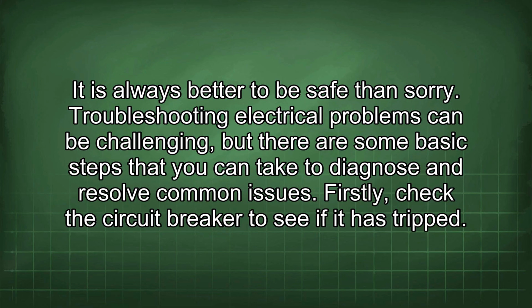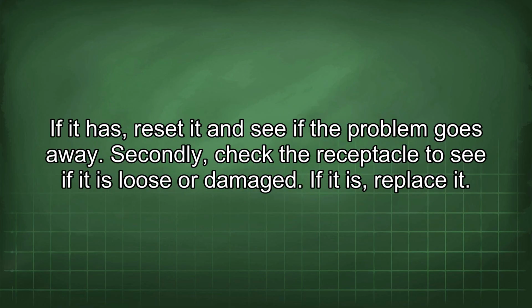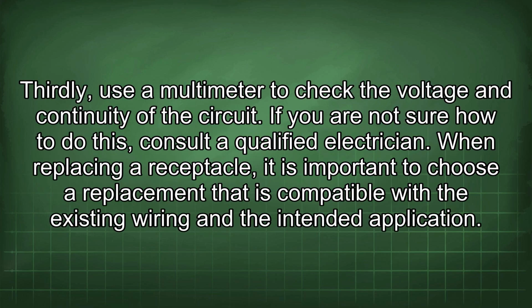Troubleshooting electrical problems can be challenging, but there are some basic steps that you can take to diagnose and resolve common issues. Firstly, check the circuit breaker to see if it has tripped. If it has, reset it and see if the problem goes away. Secondly, check the receptacle to see if it is loose or damaged. If it is, replace it. Thirdly, use a multimeter to check the voltage and continuity of the circuit. If you are not sure how to do this, consult a qualified electrician.